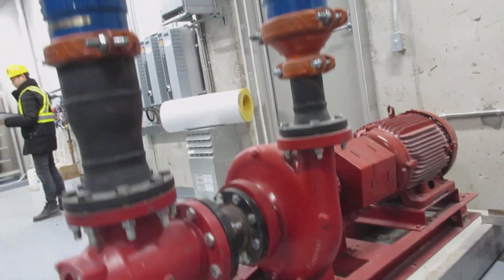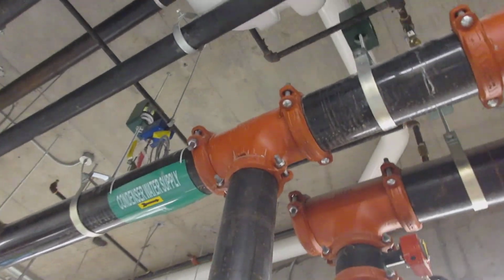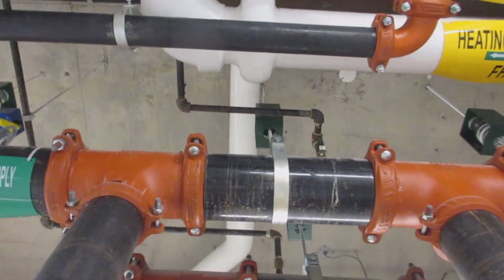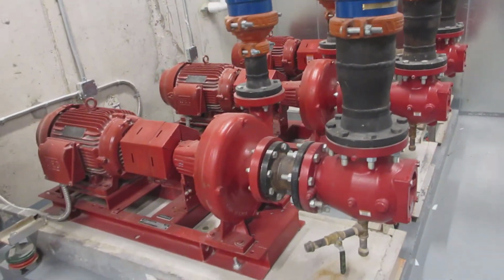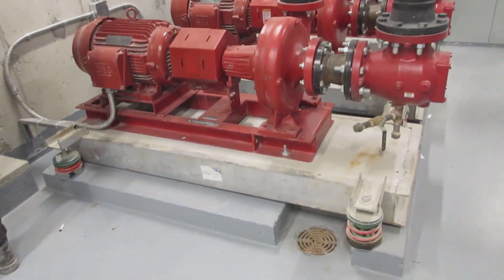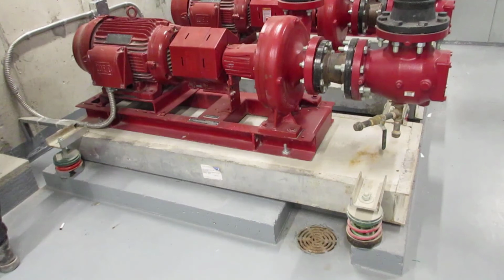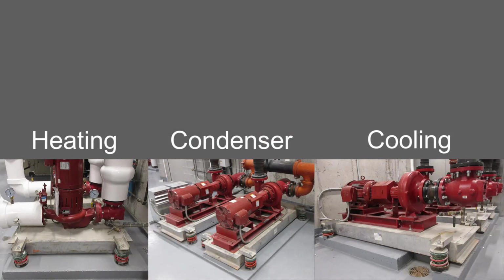I'll tilt the camera up towards the ceiling so you can see that the pipes above are supported with spring hanger isolators, which help to float the entire system and reduce vibration transmission to structure. Back where we started, I'll make one more comment. We see the suction elbows are not supported on the bases, which reduces the amount of weight the springs have to support. So now we come to the fun part.